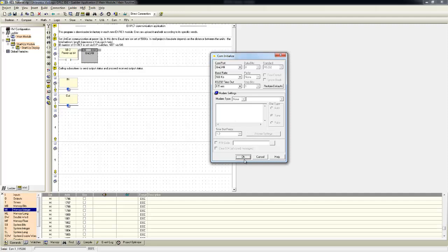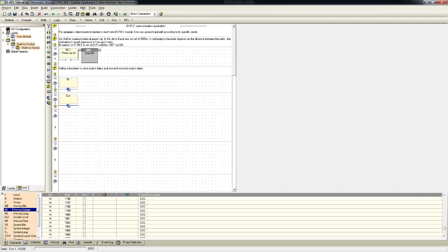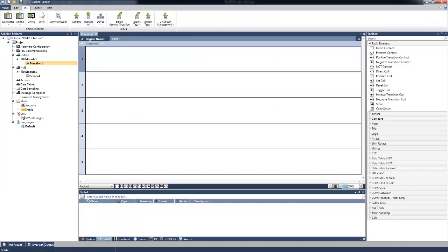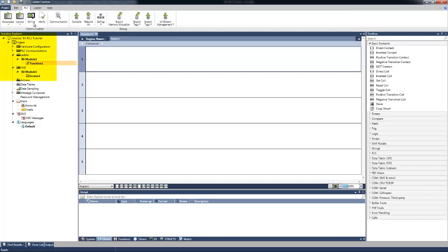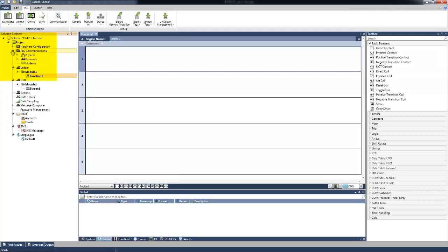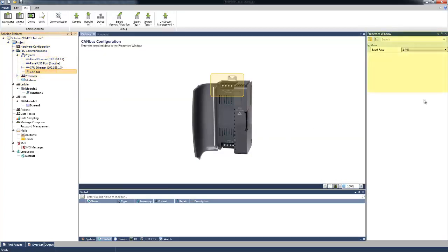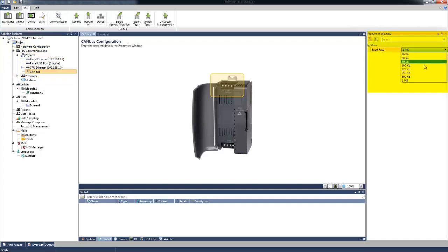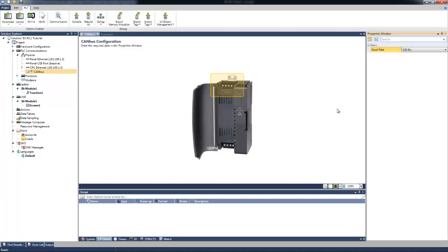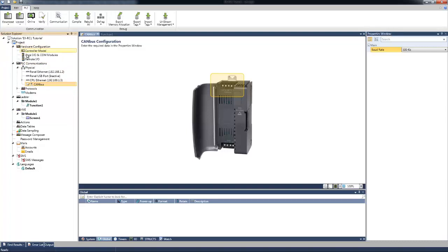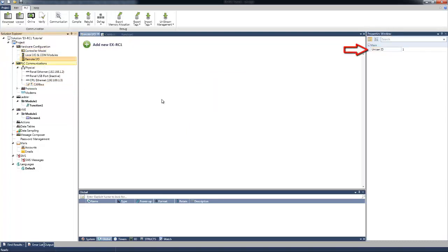Let's open Unilogic. In Unilogic, we will set the CANbus baud rate from the Solution Explorer, PLC Communication, Physical, CANbus. We'll set it to 500 kilobits in the Properties window. Let's select the Remote I/O from the Solution Explorer, Hardware Configuration. We can see that by default, the UniStream CANbus ID is 1.